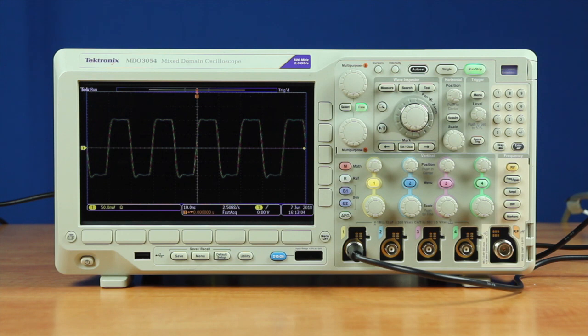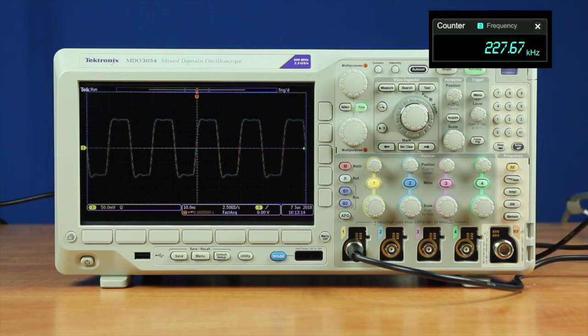Here we are using FastAcq mode on the 10 nanosecond per division scale looking at a 50 MHz square wave. We're going to measure the waveform capture rate with the same counter we'll use on the Regal. It's shown here overlaid on the display.